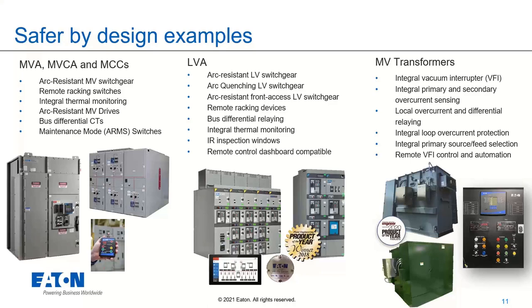And then on the transformer side, and what we're going to focus on for the remainder of the presentation, we're really looking at some of this integrated equipment, these integrated vacuum interrupters. So I have the VFI, the vacuum fault interrupter. So integrating that into the transformer, integrating that overcurrent sensing, integrating that relaying, and also doing similar remote racking or remote switching in those cases. And what can we do with that technology, implemented in a transformer or in a substation lineup or whatever your MV gear is? How can that truly benefit you from an arc flash perspective?